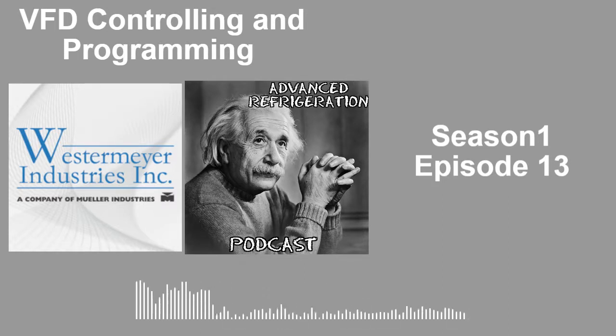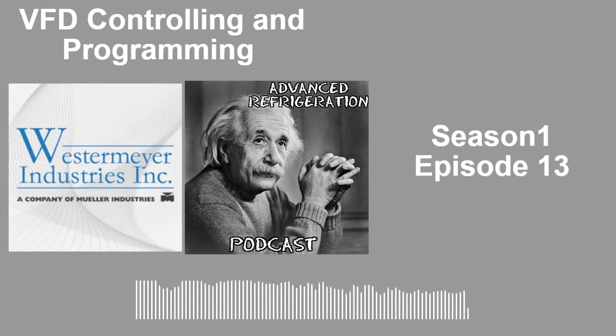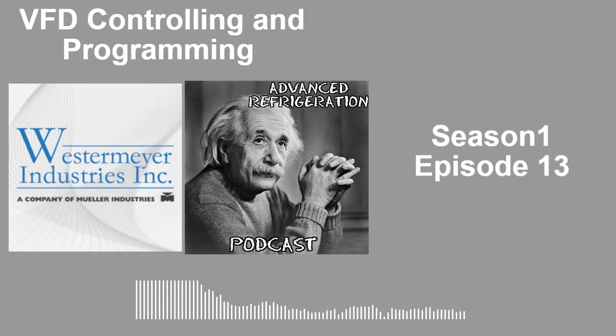So that's a basic overview. Most of the time you're going to see a lot of Danfoss stuff. With the Danfoss drives, you could change the transducers and temp sensors, like Brett was talking about on the NIDEC ones. The Danfoss ones, you could change everything but the temp sensor. You could change it to a CPC transducer, a Novar transducer, a Danfoss transducer. All you got to do is change the scaling inside the drive itself.